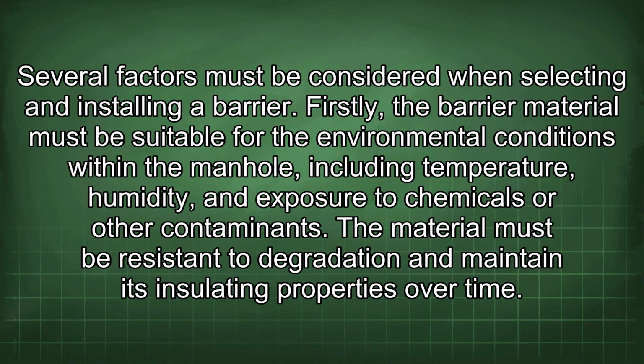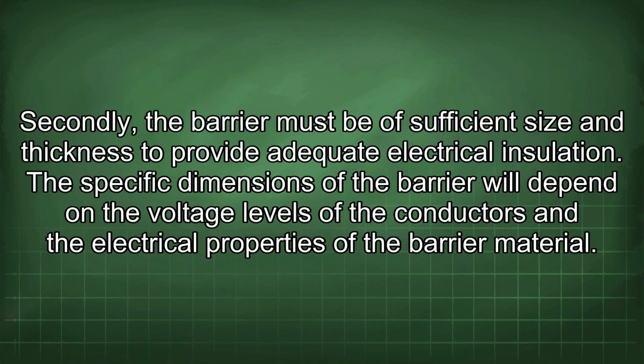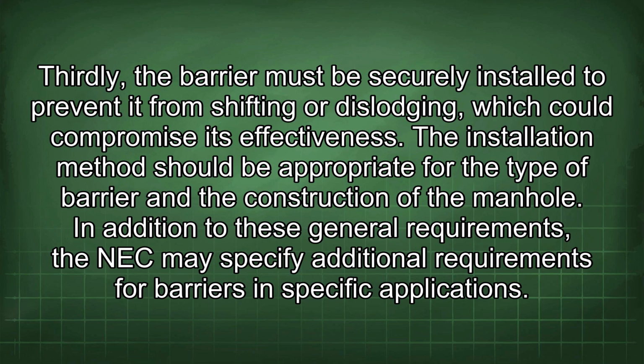Several factors must be considered when selecting and installing a barrier. Firstly, the barrier material must be suitable for the environmental conditions within the manhole, including temperature, humidity, and exposure to chemicals or other contaminants. The material must be resistant to degradation and maintain its insulating properties over time. Secondly, the barrier must be of sufficient size and thickness to provide adequate electrical insulation. The specific dimensions of the barrier will depend on the voltage levels of the conductors and the electrical properties of the barrier material. Thirdly, the barrier must be securely installed to prevent it from shifting or dislodging, which could compromise its effectiveness. The installation method should be appropriate for the type of barrier and the construction of the manhole.